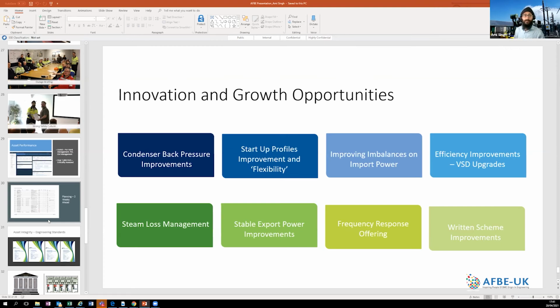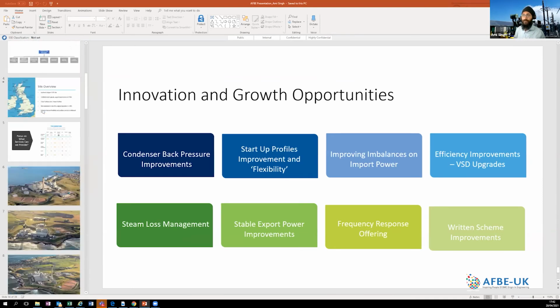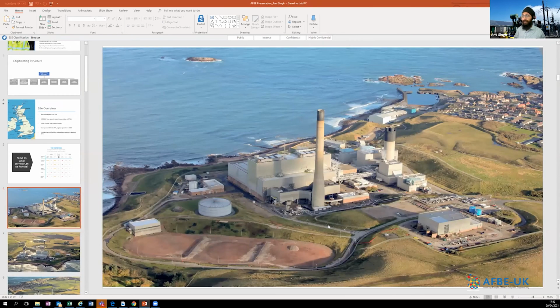We've been able to identify issues even before an alarm comes in. For example, a CW bearing temperature deviation of 5 degrees, such a minute difference between the delta T - what it should be and what it is - allows us to drive alarms even before it hits an alarm set point, which may only hit in another 10 days' time. So GE Smart Signal technology is something we use quite comprehensively across the whole thermal fleet. We're quite fortunate because everything, as you can see in the slides, is constrained to one small area, and it's heavily monitored by analog signals, all fed back to GE Smart Signal for monitoring and analysis.